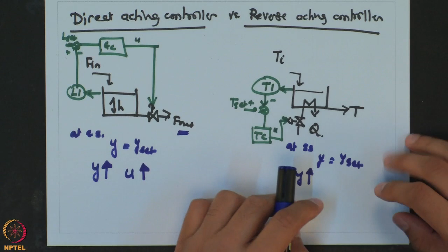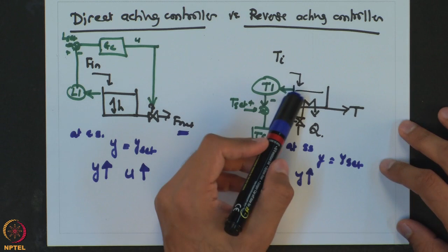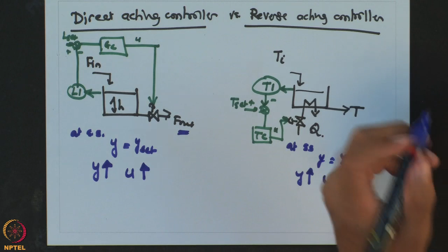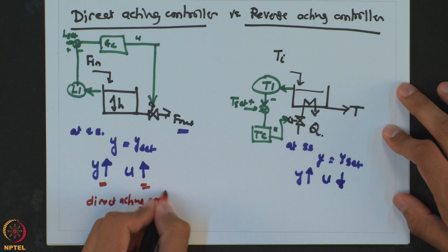Now, look at this case of the stirred tank heater. Let us say the y increases beyond the set point, that means the temperature inside this tank is above the desired value. Now, what should the controller do? It should actually cut down on the heating duty supplied to the system. That means the controller output should decrease. So, now you can notice the difference between these two systems. Here an increase in the output causes an increase in the controller output, therefore, it is known as a direct acting controller. In this case, an increase in the output causes a decrease in the controller output, therefore, it is known as a reverse acting controller.